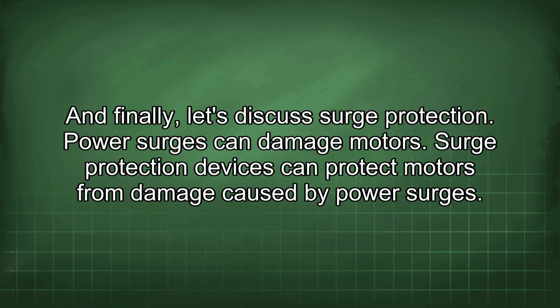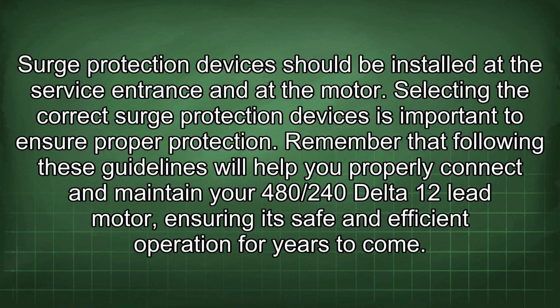And finally, let's discuss surge protection. Power surges can damage motors. Surge protection devices can protect motors from damage caused by power surges. Surge protection devices should be installed at the service entrance and at the motor. Selecting the correct surge protection devices is important to ensure proper protection.